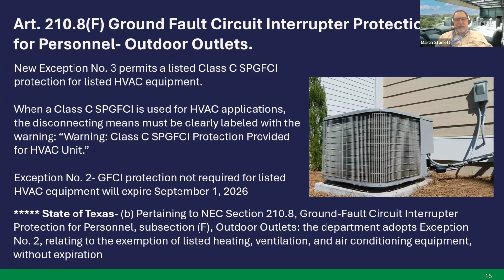the state of Texas will continue the exception for no GFCI protection for listed HVAC equipment, and because it'll be a statewide rule, the city of Austin will also follow the same enforcement plan. So as it stands, come September 1st, in the state of Texas, if this rule goes through, which I'm sure it will, you will not have to GFCI protect the HVAC equipment until that rule gets changed. Next slide.